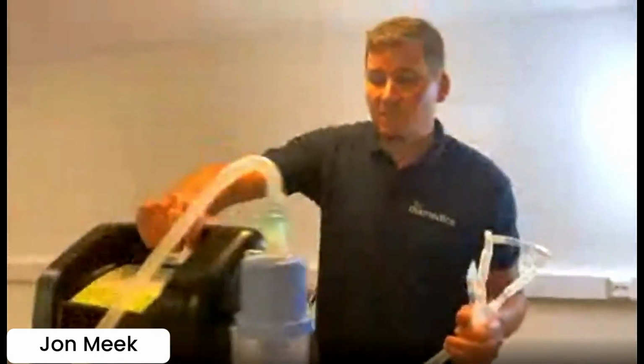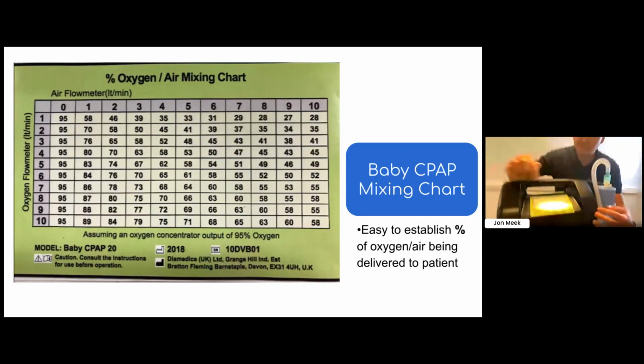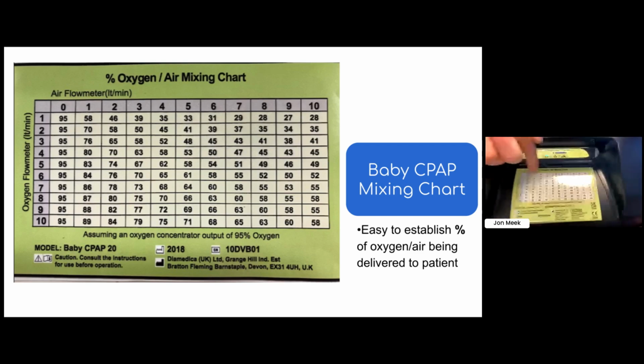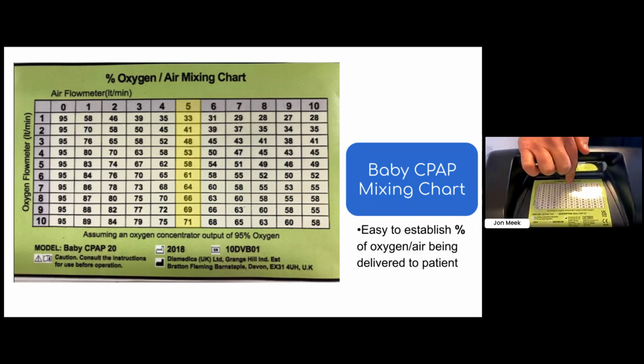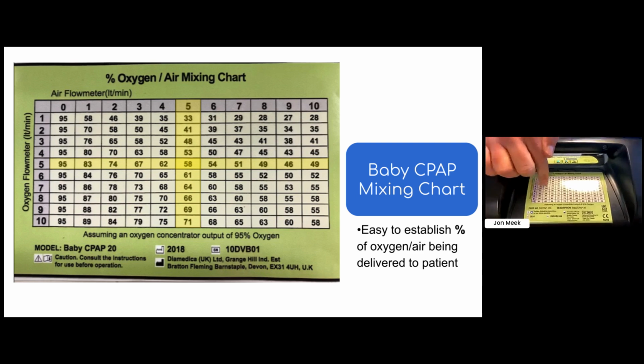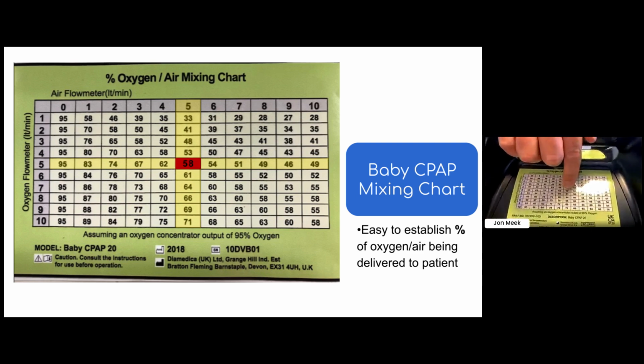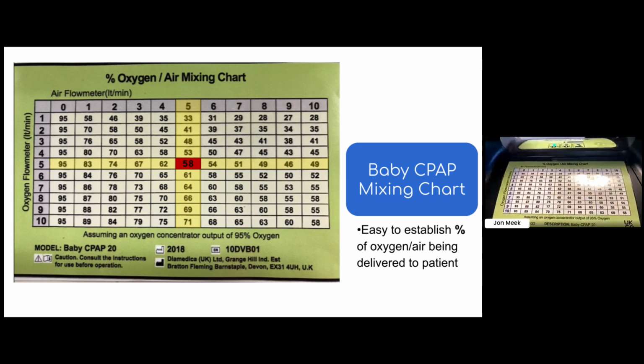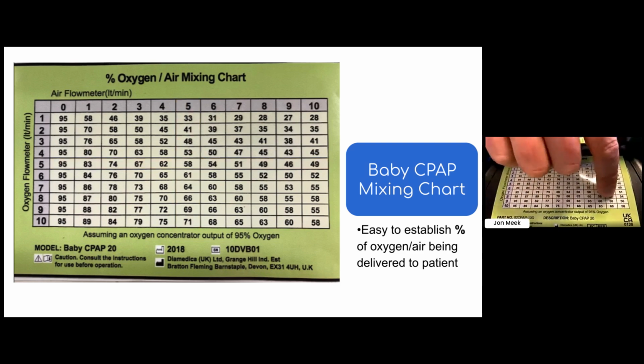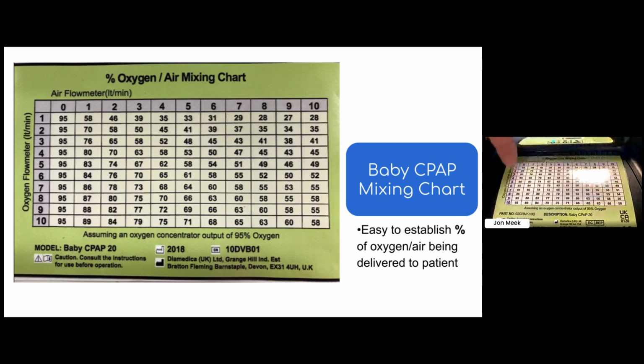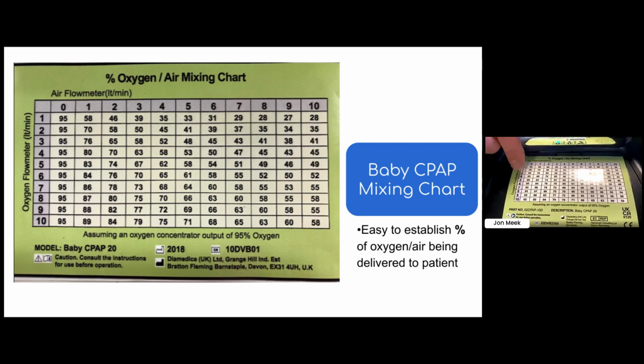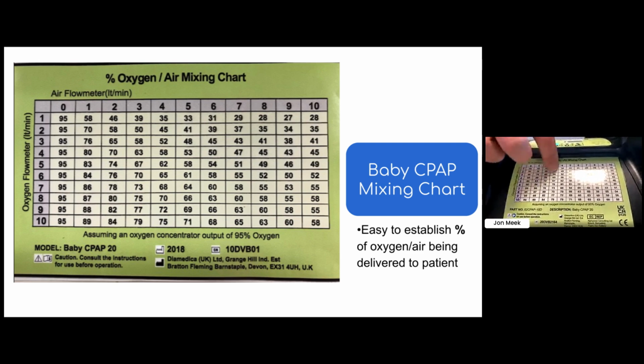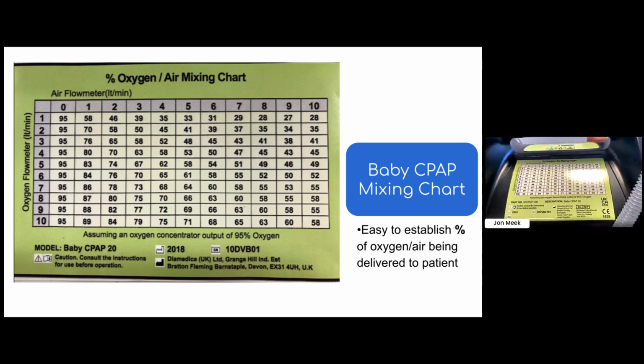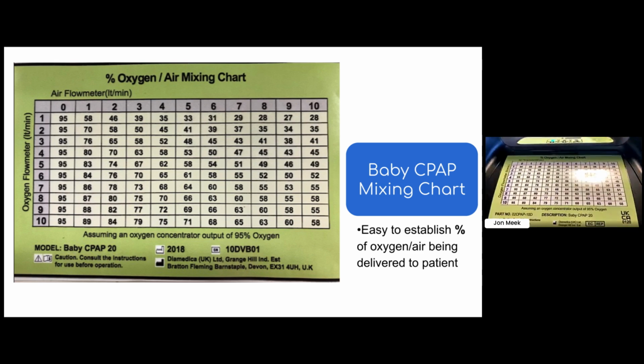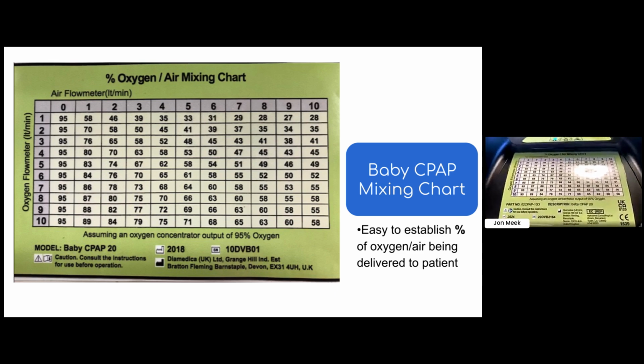I will just go through the mixing chart again to give you another look. So we set to 5 and 5. As I said before, I set the airflow meter to 5 and the oxygen to 5. If you meet in the middle, it comes to 58%, and that's 10 liters a minute at 58%. If you need higher or lower flows, you can increase to 9 and 9, or lower flows, depending on what pressure you're going for, 3 and 3. You can still generate different pressures and flows at different safe FiO2 levels, which is really important, and it makes it really easy to understand how to set.